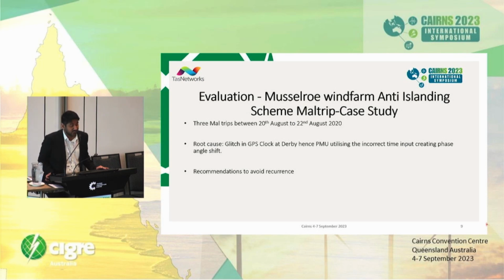So there was a glitch, and the PMU utilized the wrong time sample. Due to the angular phase shift, it would give separate voltages at one time, while the PMU at Headspin was seeing something else and Derby was seeing something else. So it caused a maltrip.